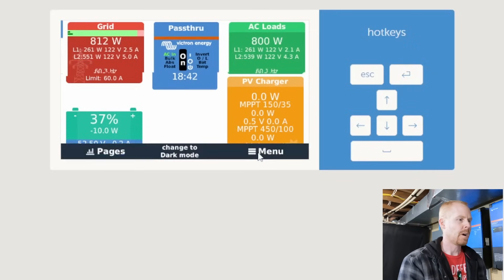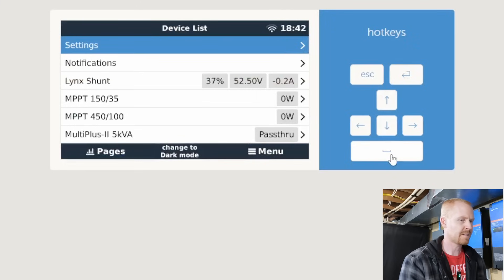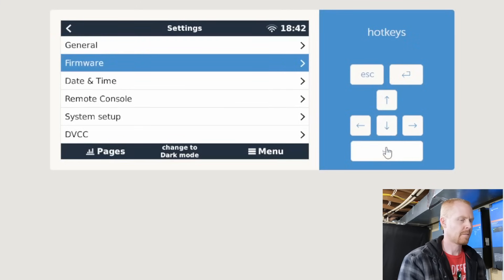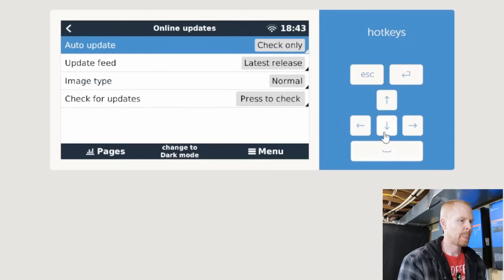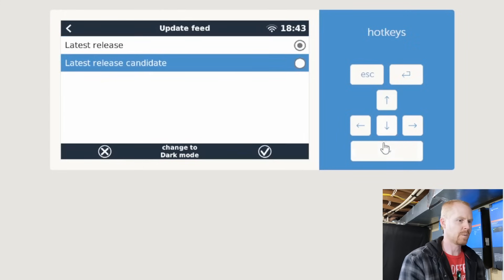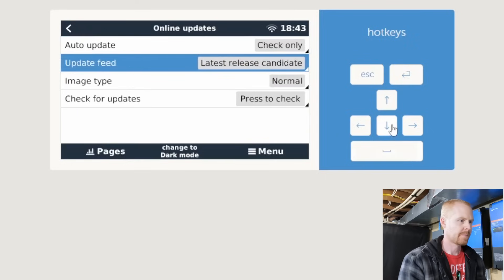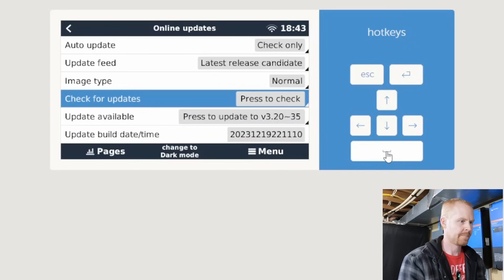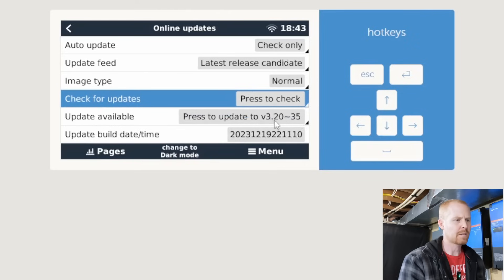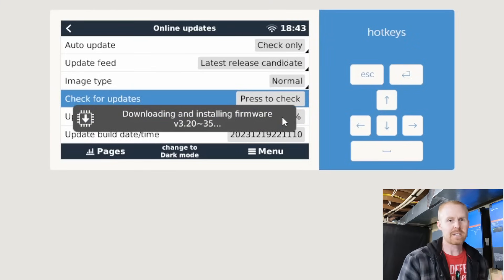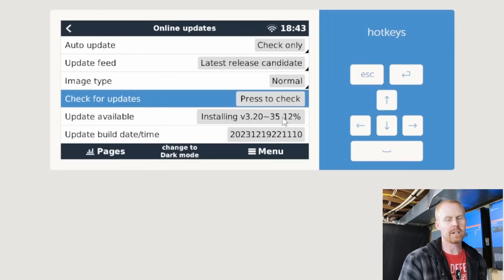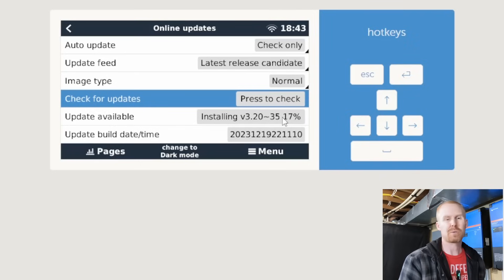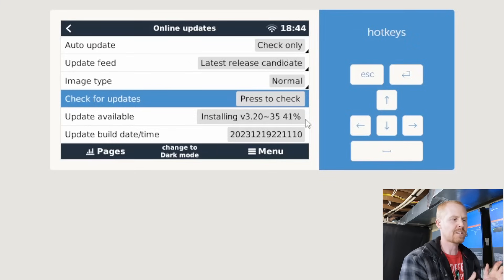So we need to download the latest firmware. So go to settings, firmware, online updates. And we need to change the update feed from latest release to release candidate. And then check for updates. And it says there's an update. And I believe I said 3.20 update 18. So this is update 35, so we're going to install this. And it's probably going to take a few minutes for it to download the firmware and install. I believe it runs through and it reboots the Cerbo twice, usually. So we'll take a look at it once it finishes installing and gets back up and running.